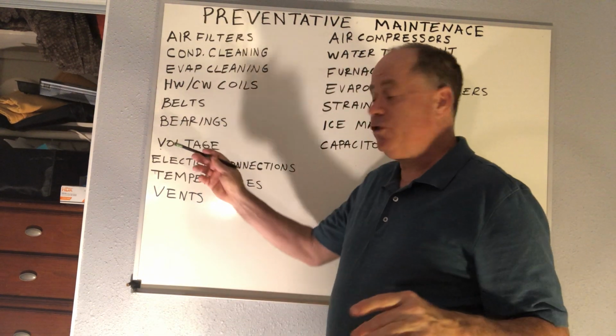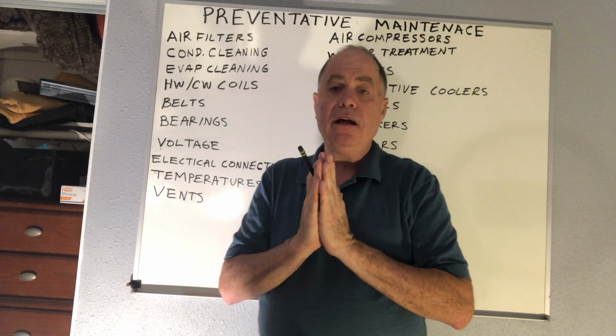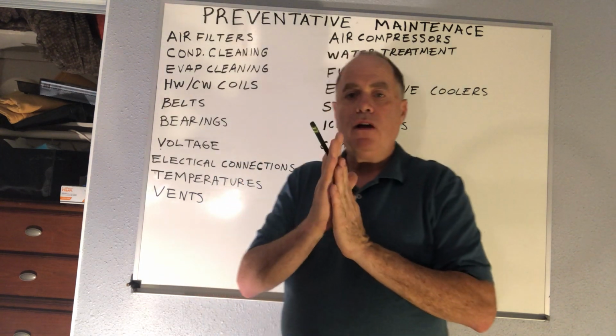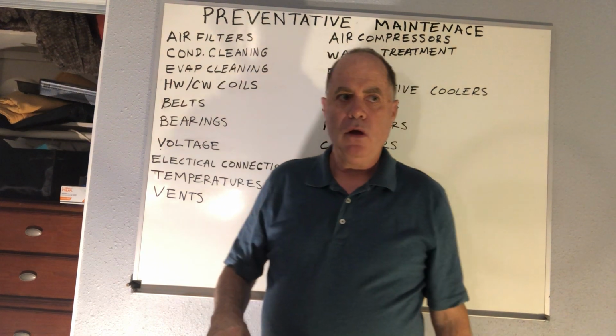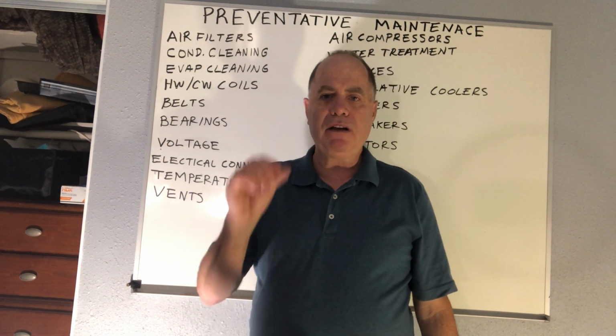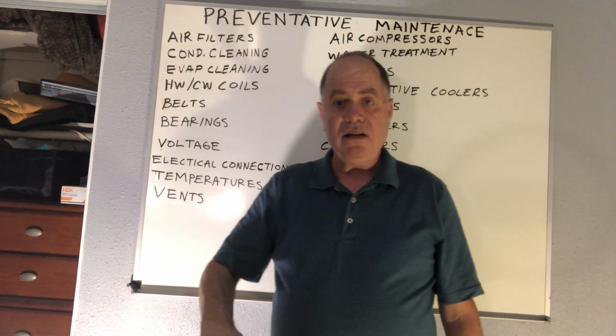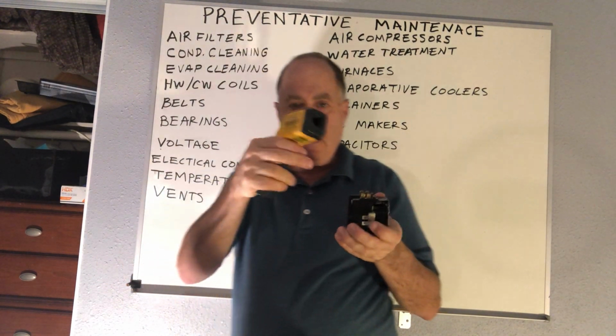Okay? Now, low voltage means a loose or dirty connection, a contact that is pitted or blackened. Any of these things cause a loose connection and will cause voltage drop. Okay? And anytime you have a loose connection or a pitted contact, it becomes like a baby heater, and it uses up a little bit of that voltage. It's almost like two loads in series. Taking your infrared gun and using this as troubleshooting and maintenance, and shooting terminals on electrical panels, on contactor terminals and things like this, can show you where some loose connections are. So this infrared gun is very handy for finding loose connections.